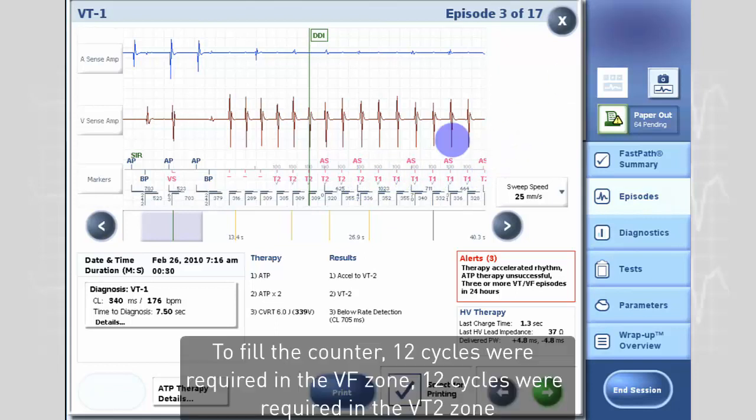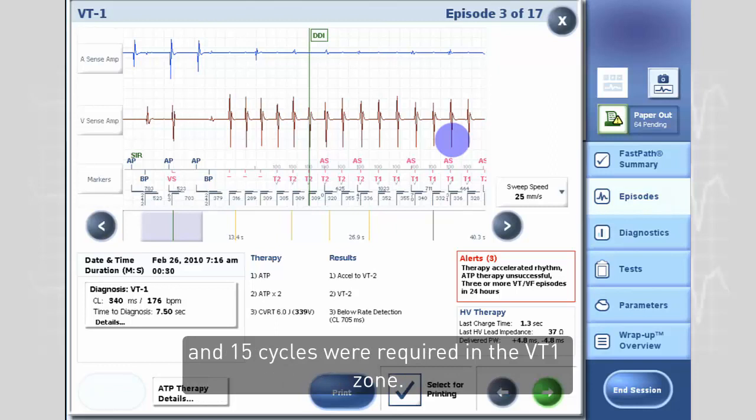To fill the counter, 12 cycles were required in the VF zone, 12 cycles were required in the VT2 zone, and 15 cycles were required in the VT1 zone.